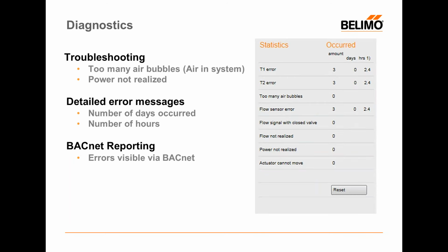We have something called the status page, and the status page is where we can do some troubleshooting, take a look if we've had any problems with our temp sensors, possibly there was air in the system during startup, things of that nature. If maybe the valve hasn't been adapted or configured properly, or our signals aren't matching and we're seeing flow where we might think the valve is closed. You can see how these errors are detailed not only in days but in hours and a number of occurrences. And on the BACnet side, these errors will be visible via BACnet bits.